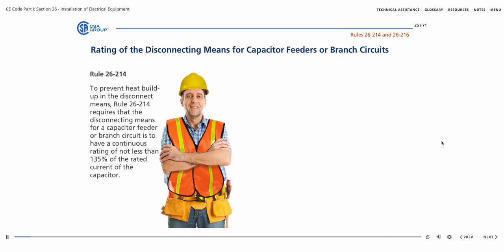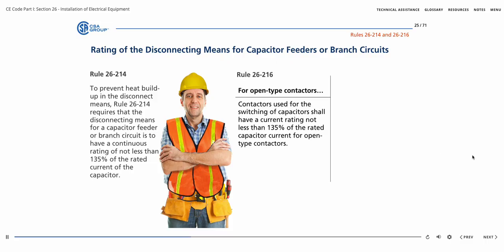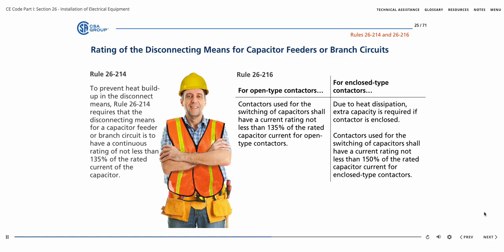To prevent heat buildup in the disconnecting means, Rule 26-214 requires that the disconnecting means for a capacitor feeder or branch circuit is to have a continuous rating of not less than 135% of the rated current of the capacitor. Contactors used for the switching of capacitors shall have a current rating not less than 135% of the rated capacitor current for open-type contactors. Due to heat dissipation, extra capacity is required if the contactor is enclosed. Contactors used for the switching of capacitors shall have a current rating not less than 150% of the rated capacitor current for enclosed-type contactors.